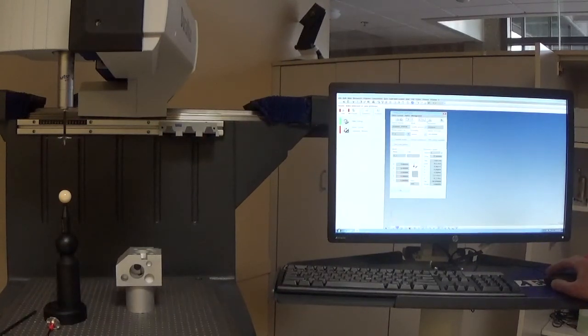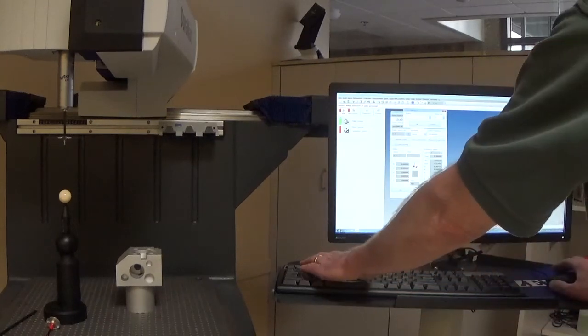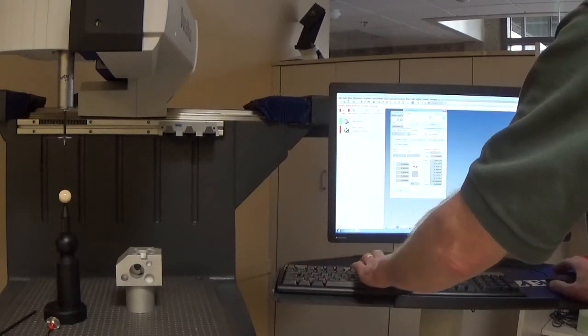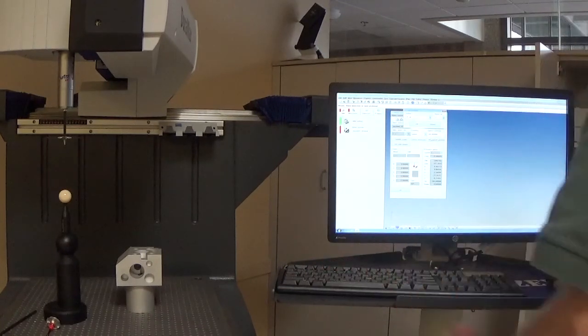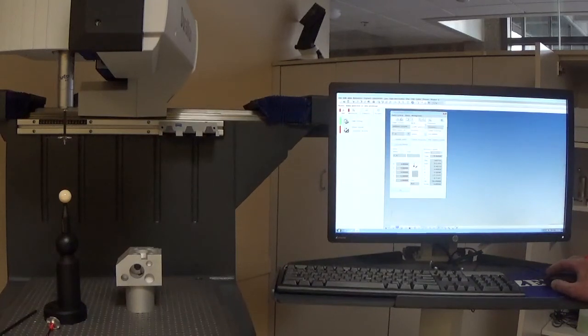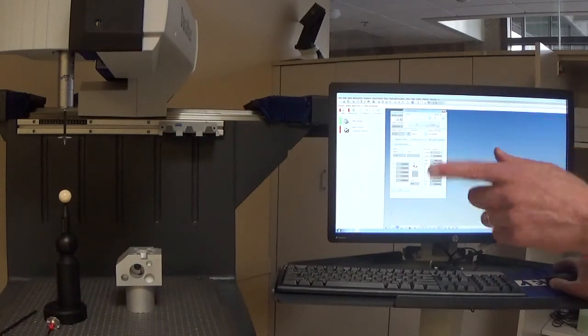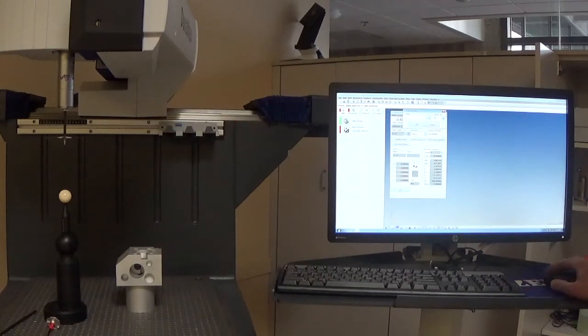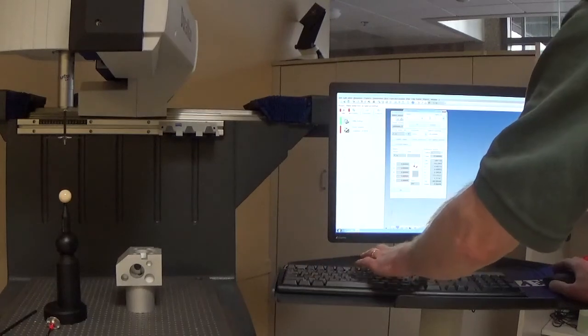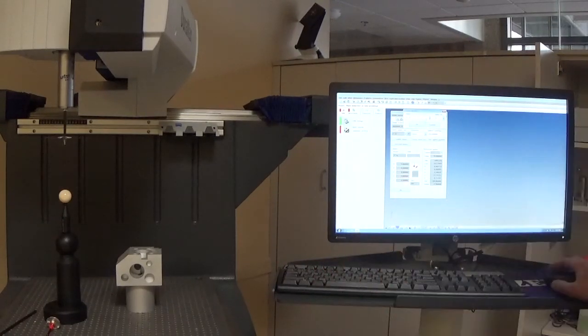And I'm going to add my other stylus to my stylus system. So I click on the Insert New Stylus button. And my second stylus is going to be number 2. And that's in the Y plus direction. So I name that 2 underscore plus Y, and I click OK. And then I want to insert my third stylus, and that's going to be stylus number 5. It's the one pointing to the left, so it's going to be my X minus. So I'm going to name that 5 underscore minus X. And I click OK.